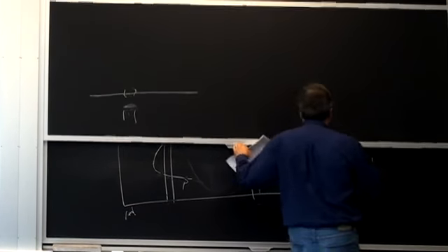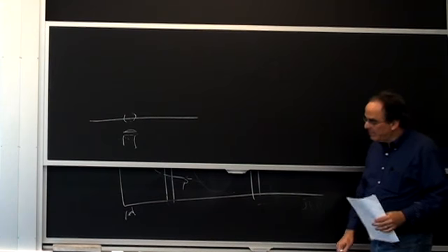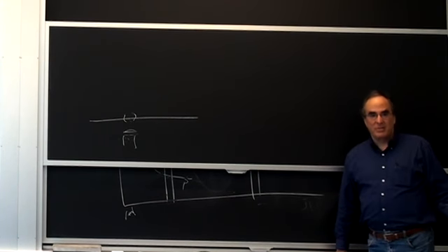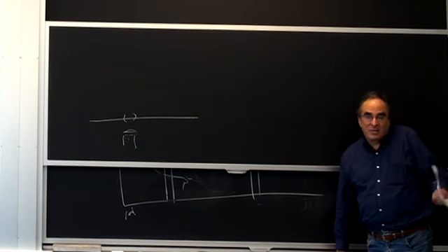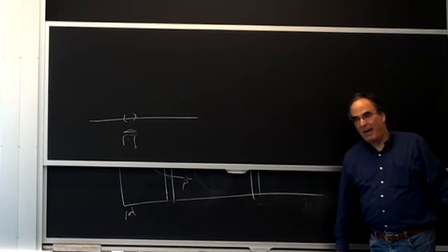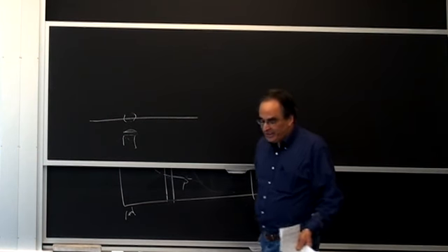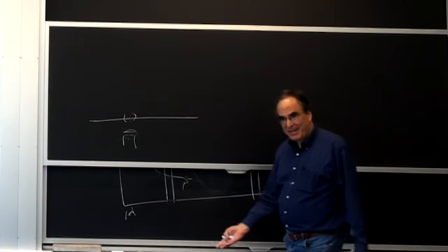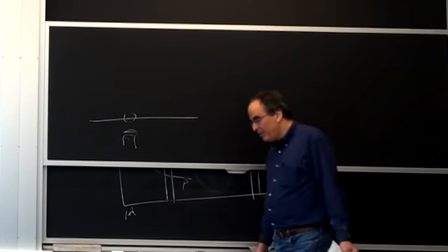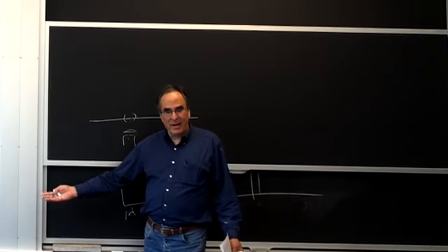Using the monochromator satisfies my rule that you want something that's always going to work. Because what is a monochromator? It's a grating in a box. And if the grating drive isn't working well, you knew that before you started the experiment. And if the photomultiplier isn't working well, it's the same thing you do with LIF.